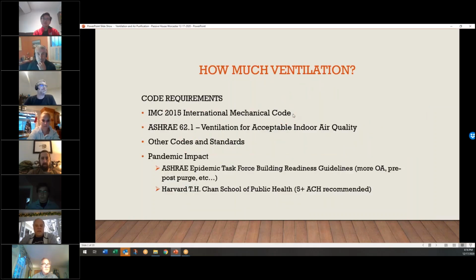So I started out basically with ventilation, right? How do we figure out how much air we need? We typically will go to standards, like the Massachusetts Building Code, which is currently referring to the International Mechanical Code 2015 for ventilation requirements. It also is very similar to ASHRAE 62.1, which the IMC will generally cover a lot of. ASHRAE has some more different types of buildings that the IMC might not call out, all the different possible scenarios you may run into. So we tend to use both, but they usually will match on similar type spaces.